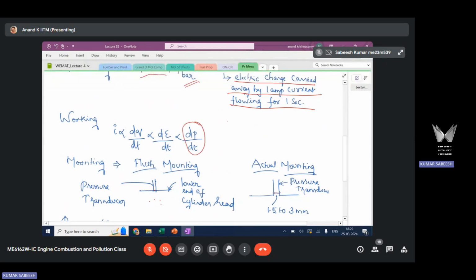So you apply pressure on the diaphragm, dp by dt is the applied pressure. Because of that, the crystal gets strained by d epsilon by dt. Because of the strain, you generate an electric charge dq by dt. So there is a flow of current I in the external circuit, and this I is proportional to dp by dt. To remove the proportionality symbol, you introduce a constant, which is the sensitivity of the equipment. So I is equal to dP by dt multiplied by GS. GS is the sensitivity of the equipment.